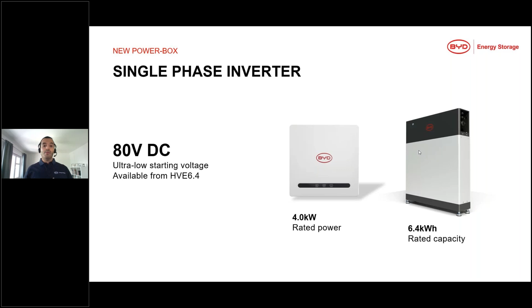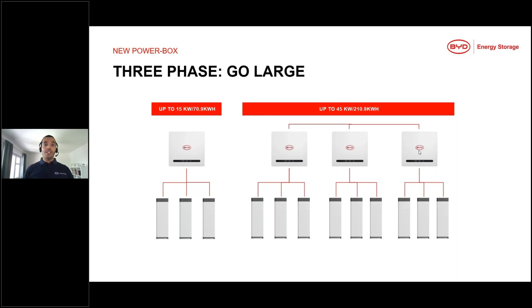One battery to one inverter, one battery to one inverter, one battery to one inverter, all those inverters connected in parallel. Or you can have up to three HVE connected in parallel, and those three battery HVE towers connected in parallel to one inverter, and that times three. This gives you quite some capacity and also quite some power, up to 45 kilowatt if you have three times the three-phase inverter, and up to 210 kilowatt hours if you have 9 battery towers.